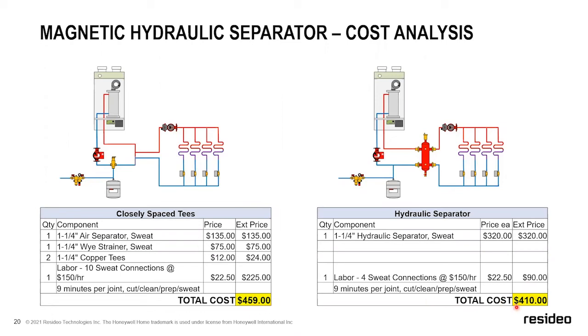So it's about a $50 savings, plus you're adding that magnetic separation, which again, as we move over to variable speed pumps, it's becoming more and more important. So this can be adapted to whatever your labor rates are, whatever your time is. What you'll find is this number is still going to come out to roughly the same cost, even if you change your labor rate and your time. This is just an example that I've used off a national average. So just something to keep in mind. Yes, the upfront cost is more, but when you factor everything, it ends up being roughly the same or less, and you're providing a lot more value to your system.